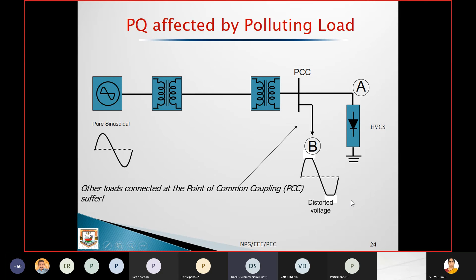Now, what are the effects on EV and the grid when connecting to the electrical grid? When you connect more charging stations, all charging simultaneously, you get distorted current and voltage. This distorted voltage is injected into the utility grid. Due to this, there is a chance of harmonics, sag, swell, voltage imbalance, flicker, notches, and transformer overloading. These are the different possible effects of EV on the grid.